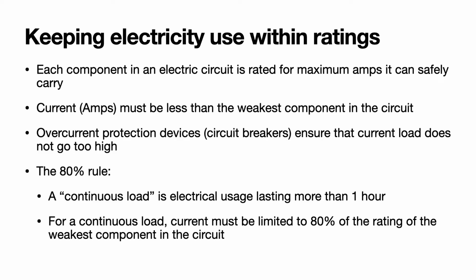What's called an overcurrent protection device, or a circuit breaker, is used to ensure that the current load does not go above the ratings of the weakest component. The idea is for the circuit breaker to detect that the load has gone too high and pop the circuit rather than risk having an electrical fire.